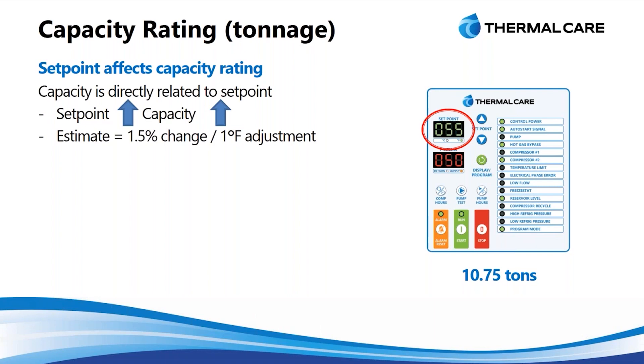In the other direction, if we need to lower the capacity below 50 degrees — if we need a colder temperature — we'll actually reduce the nominal rating below 10 tons. All of that is dependent on what the process requires. Our units have a range from 20 degrees Fahrenheit up to 80 degrees, so there's a wide variety of scenarios requiring different temperatures, and we want to be aware of the effect that has on a chiller's capacity.